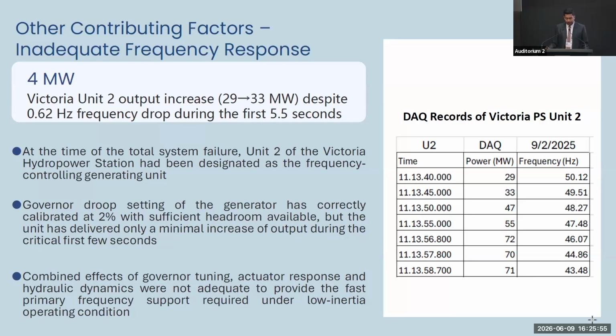Then we looked into other contributing factors which would have contributed to this cascade failure. One is the inadequate frequency response from the other generators. Victoria Unit 2 was designated. Victoria means a hydro plant. So that was designated as the frequency controlling machine which was balancing the system by that time. The droop setting has been correctly calibrated, we found that, and sufficient headroom was available at the time of disturbance, but it has given only a minimal increase of its power. That means it has increased its power by only 4 megawatts.